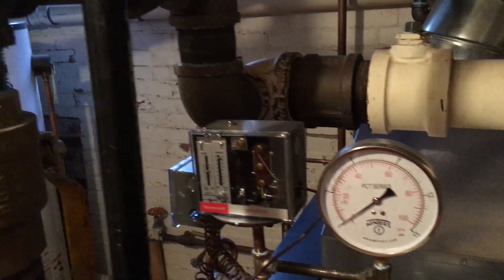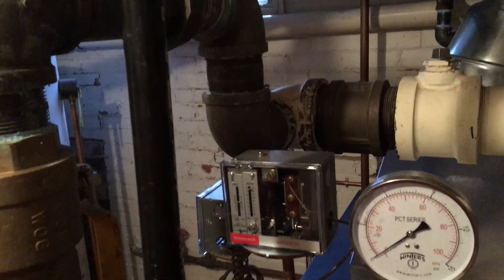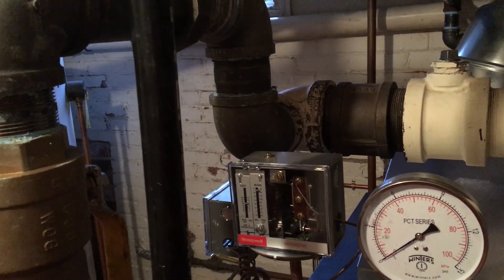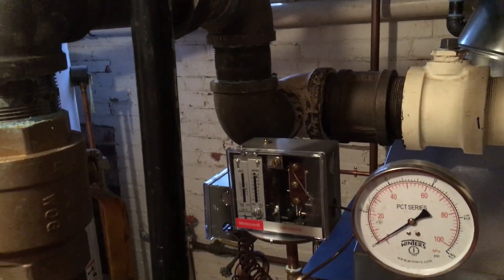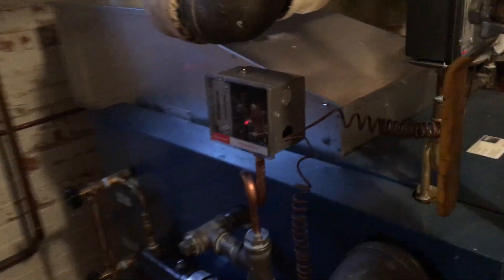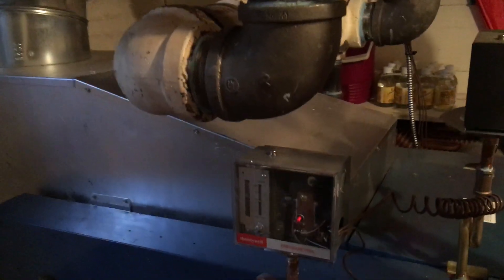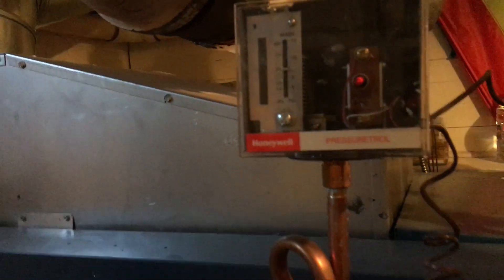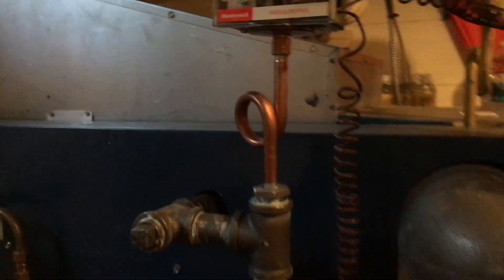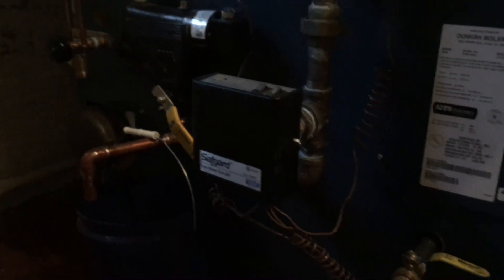There is the vapor stat set at about 16 ounces, with the differential probably eight ounces or so. Over here we have a manual reset Pressuretrol — I'm not sure where I set that, maybe five pounds or something — and it's on its own pigtail.